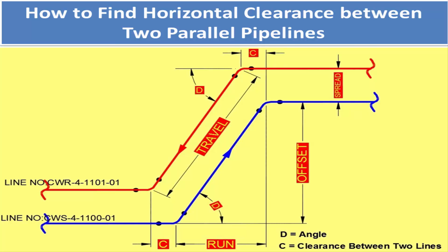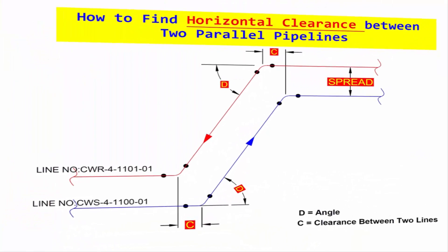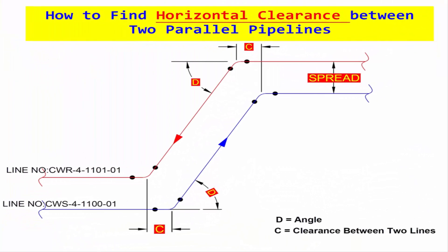In this drawing, 4-inch CWS cooling water supply line and CWR cooling water return line, two pipelines going parallelly with the same distance between two lines. Vertical distance, it means elevation difference, is called spread. D is called elbow degree, and C called horizontal distance between line one elbow center to line two elbow center.